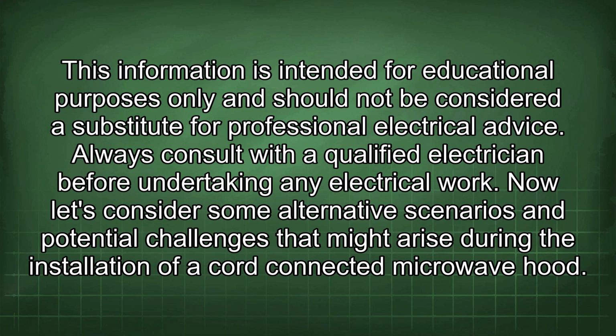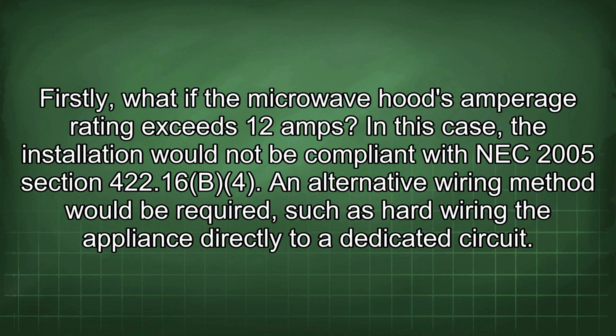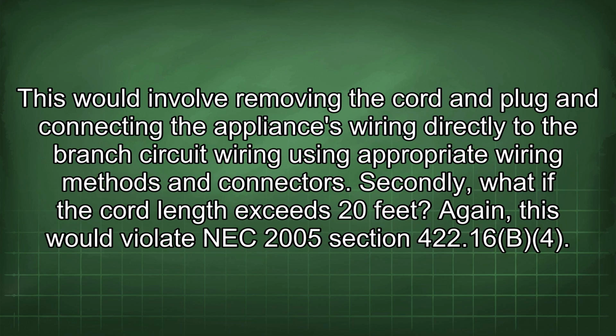Now let's consider some alternative scenarios and potential challenges that might arise during the installation of a cord-connected microwave hood. Firstly, what if the microwave hood's amperage rating exceeds 12 amps? In this case, the installation would not be compliant with NEC 2005 Section 422.16(B)(4). An alternative wiring method would be required, such as hard wiring the appliance directly to a dedicated circuit. This would involve removing the cord and plug and connecting the appliance's wiring directly to the branch circuit wiring using appropriate wiring methods and connectors.